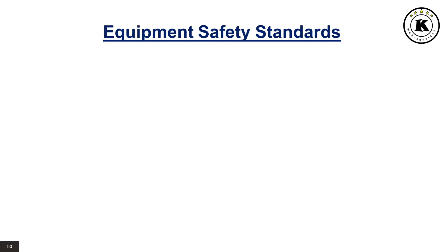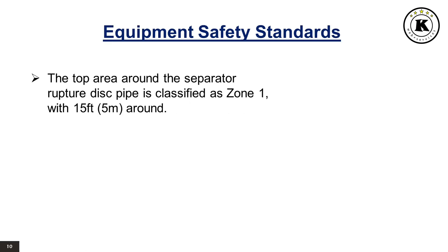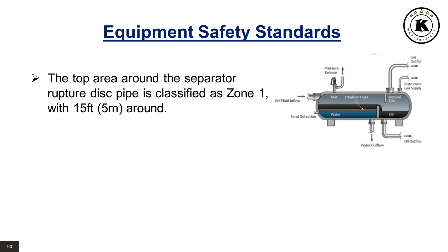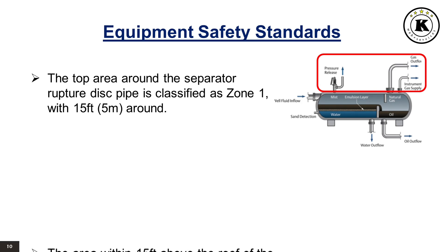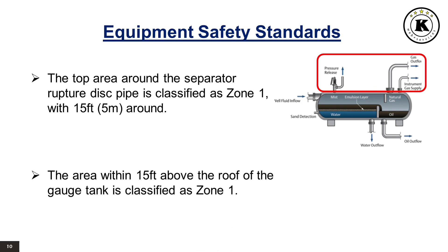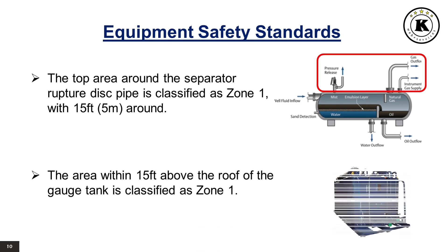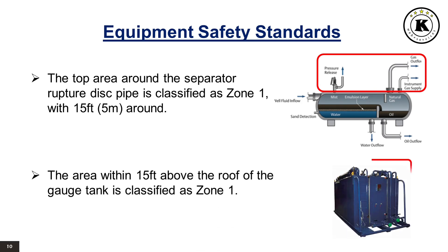Equipment safety standards: The area around the separator rupture disc pipe is classified as Zone 1, with 15 feet or 5 meters around it. The area within 15 feet above the roof of the gauge tank is also classified as Zone 1.